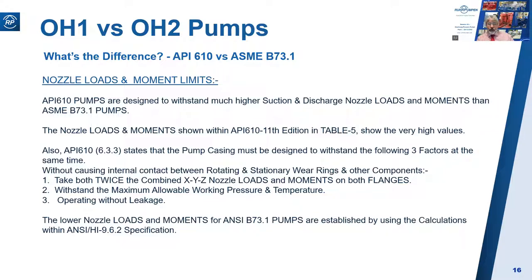This is very important because you like to use it as a pipe anchor. So having defined these allowable forces and moments, you guys frequently like to double them and say that the pumps must be suitable for 2 times forces and moments in operational situations. So this is a very good reason why ANSI pumps are seldom going to be suitable for oil and gas refinery installations. Even for non-API water type services, typically, oil company specifications for ANSI pumps tend to increase the allowable forces and moments in much the same way as they do for an API pump.